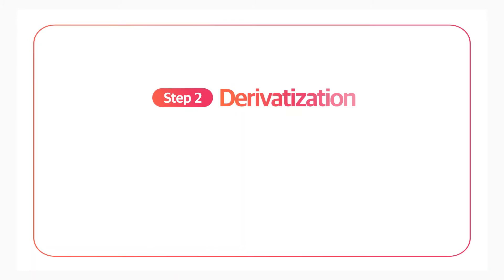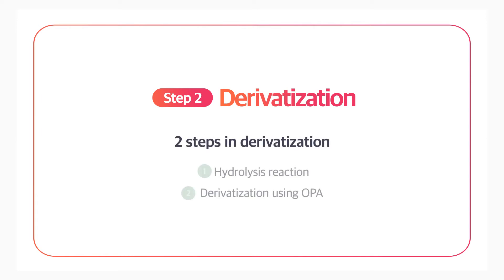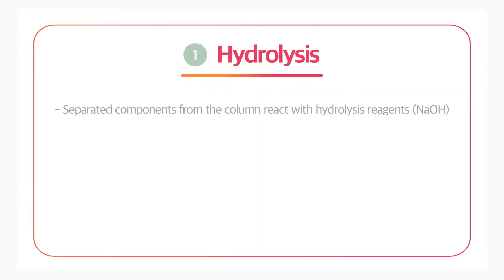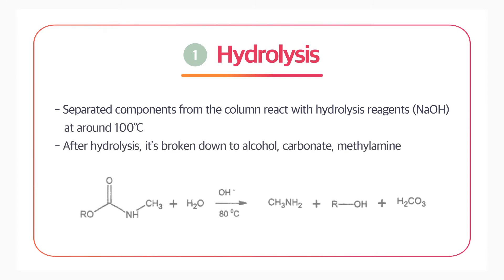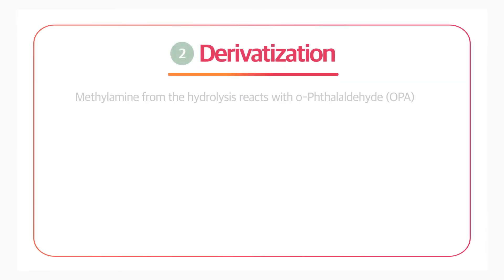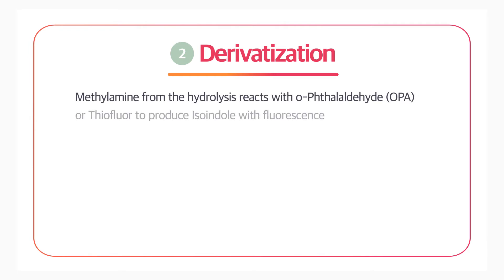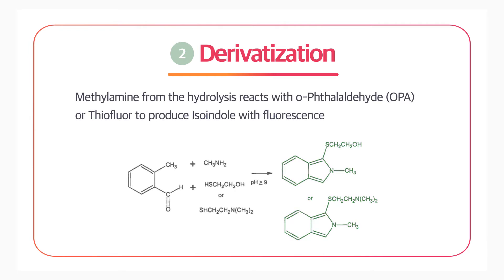After the column eluent, the separated components need to go through hydrolysis first and then fluorescence derivatization. Separated compounds from the column react with hydrolysis reagents at around 100 degrees Celsius. In the hydrolysis, the compounds break down into alcohol, carbonate, and methylamine. In the derivatization process, methylamine from the hydrolysis reacts with OPA, or thiofluor, to produce isoindole with fluorescence.